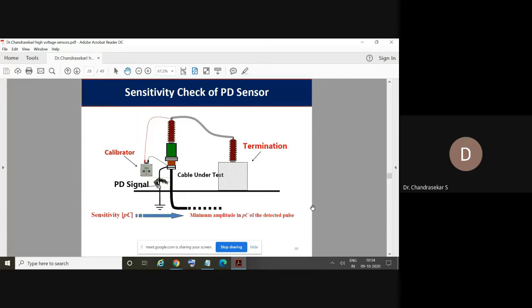For example, if it's a cable or bushing, then we need to inject that signal into the bushing, and then measure the PD signal through our sensor. If our sensor is able to capture exactly the magnitude and the frequency of the PD signals we injected, then it is working perfectly correct. So such a calibration procedure should be followed before starting the measurement. It is very, very important.